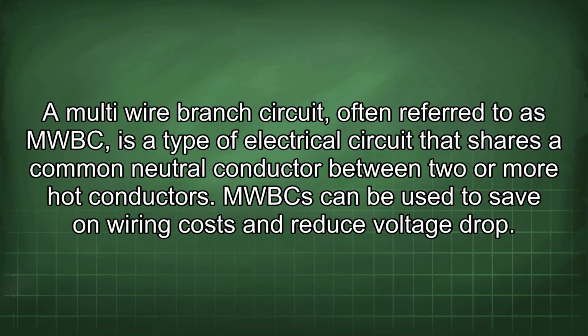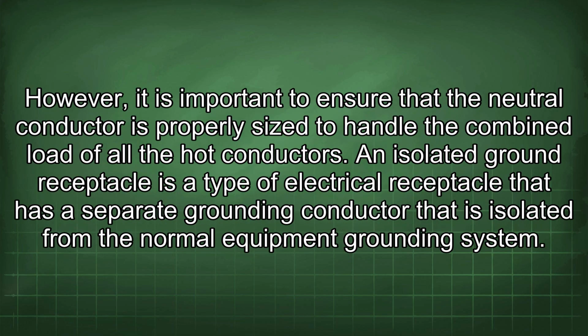A multi-wire branch circuit, often referred to as MWBC, is a type of electrical circuit that shares a common neutral conductor between two or more hot conductors. MWBCs can be used to save on wiring costs and reduce voltage drop. However, it is important to ensure that the neutral conductor is properly sized to handle the combined load of all the hot conductors.